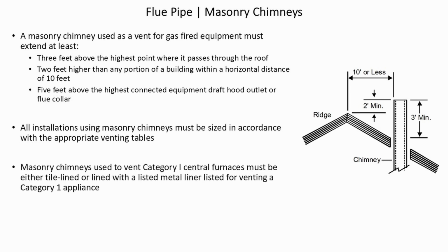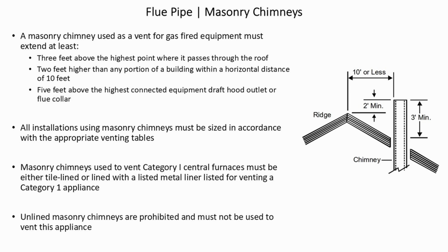Masonry chimneys used to vent Category 1 central furnaces must be either tile-lined or lined with a listed metal liner listed for venting a Category 1 appliance. Unlined masonry chimneys are prohibited and must not be used to vent this furnace.